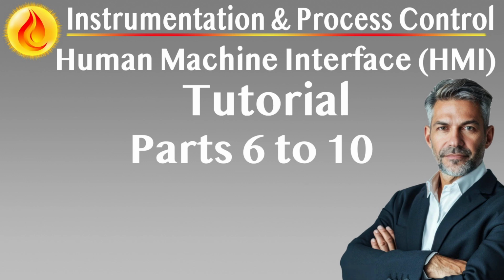Alarms are typically classified into 3 priority levels: high priority, continuous tone, immediate response required, typically tied to process safety, environmental limits, or equipment trips; medium priority, yellow, intermittent tone, action required within minutes to avoid loss of control or economic penalties; low priority, visual only, informational or early warning, may not require immediate response.